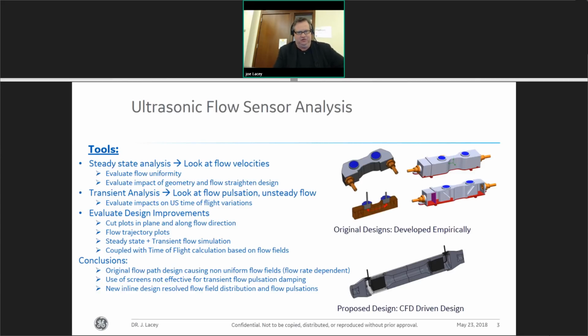So this was a project I walked into when I started in the group about 2 years ago. Over here, these are basic ultrasound flow sensors that were being developed internally to the group. They're kind of dual function. Purpose was not just to get flow, but also to get agent concentration. So when you have a patient under anesthetic, you need to give them a certain percentage of anesthetic gas, and you're feeding a medical gas at the same time, and you have no a priori knowledge of the gas that you're being fed. So it could be oxygen, nitrous oxide, in many different combinations. So that added a couple degrees of difficulty.